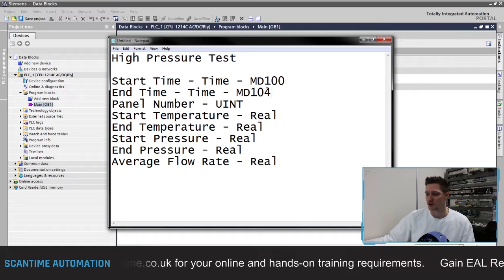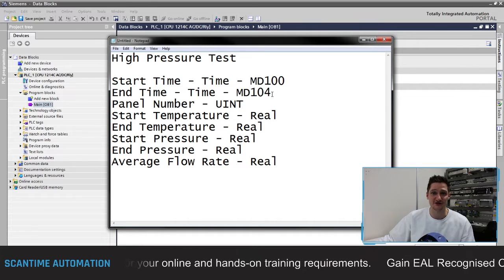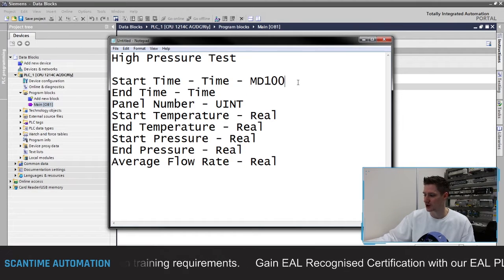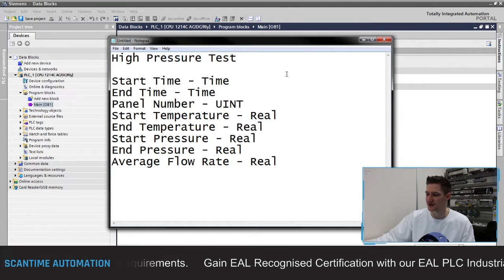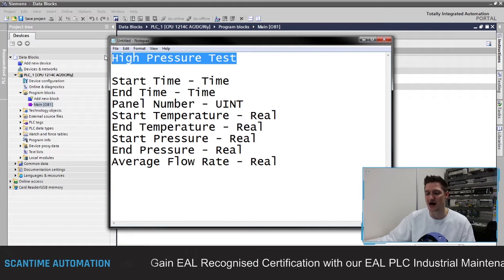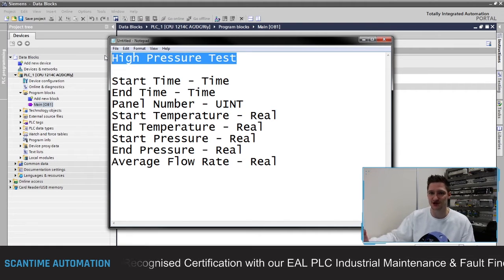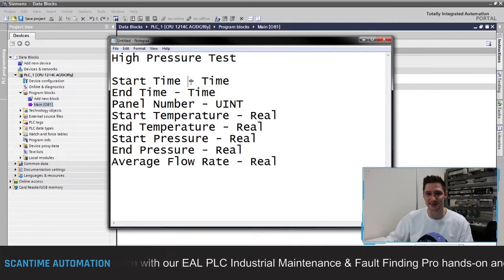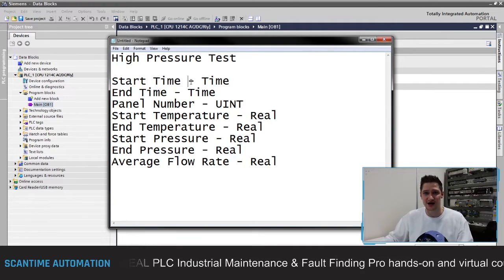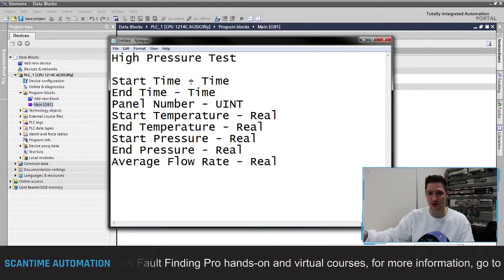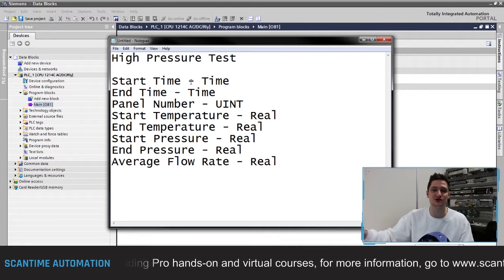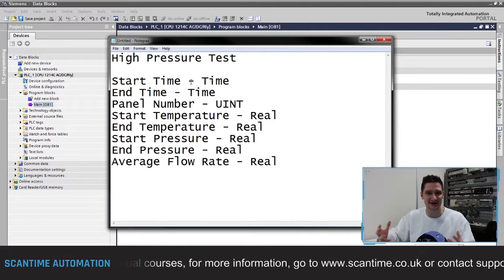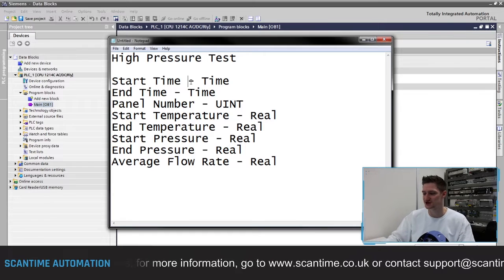We've also got the problem of overlapping areas if we're not careful. What Siemens provides us with is data blocks. We can create a data block called 'High Pressure Test', another called 'Medium Pressure Test', and 'Low Pressure Test'. Inside each data block, just like an Excel document, we can create data areas and store information inside of those, creating a structured data table to store all of this information.